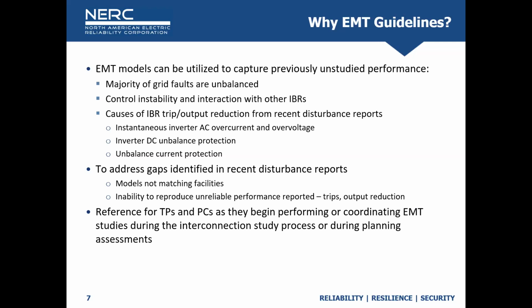Why is that important? EMT models can be used to capture previously unstudied performances - unbalanced grid faults, instability inside your plant or between other IBR plants, different causes of tripping, DC bus tripping, instantaneous inverter tripping, unbalanced current protections. All these things are kind of living in the EMT domain. They're not going to get captured in an RMS model.